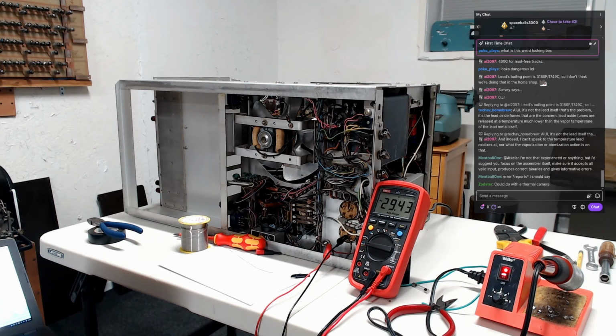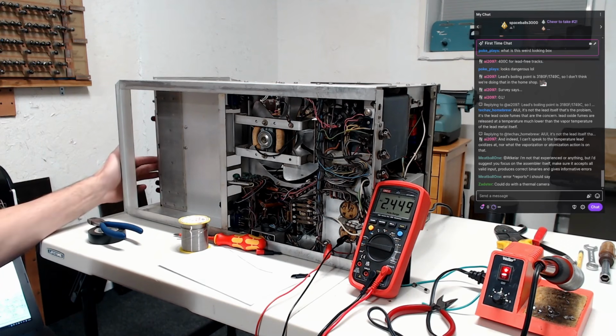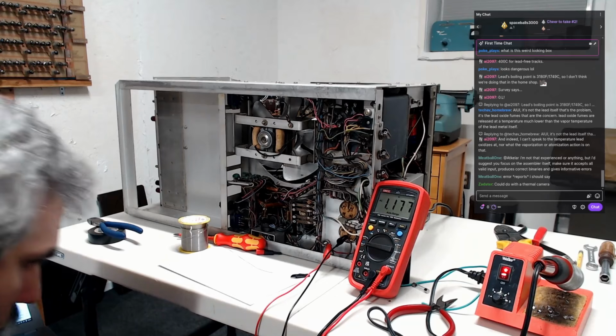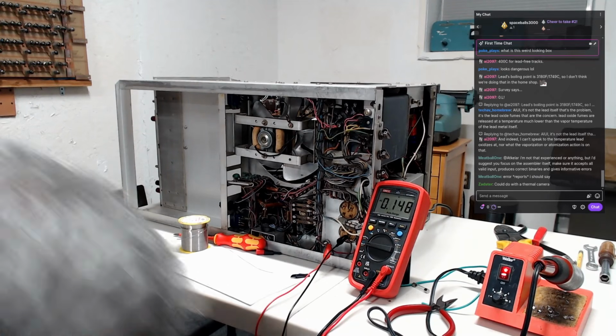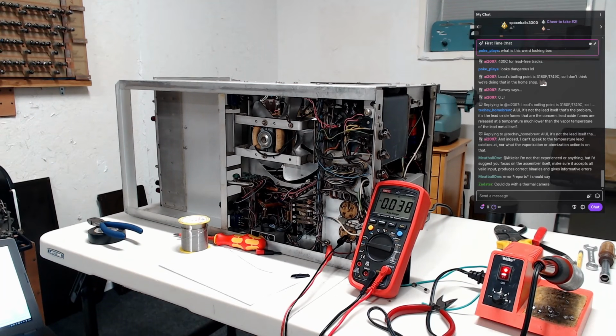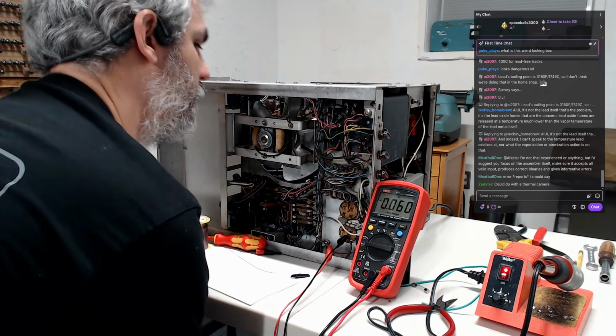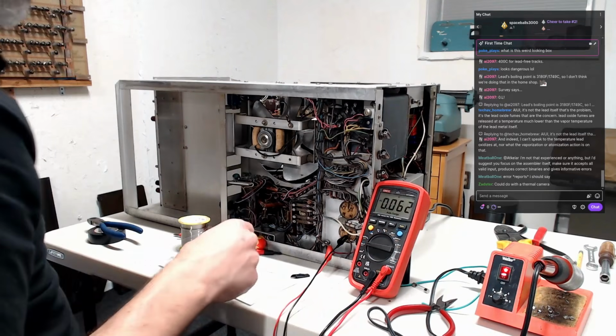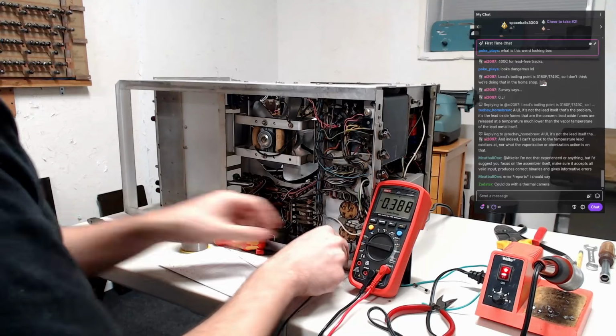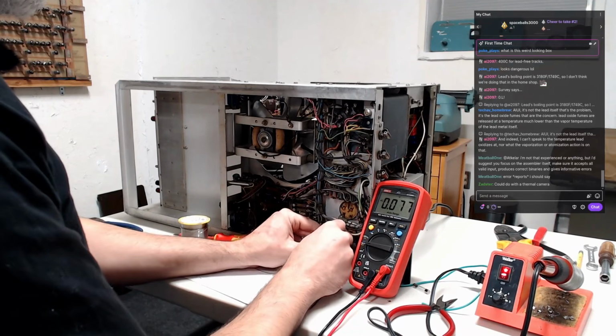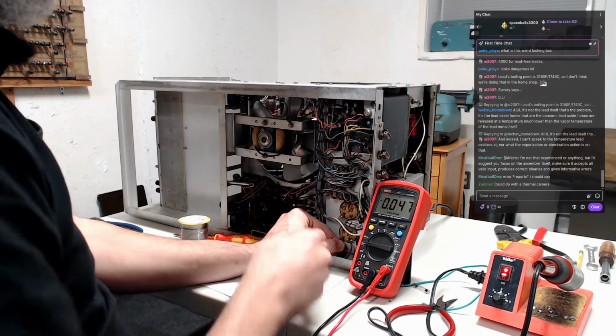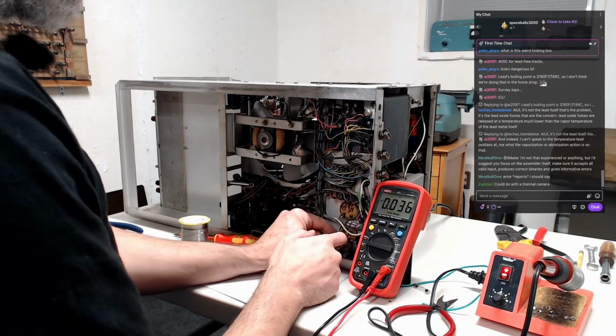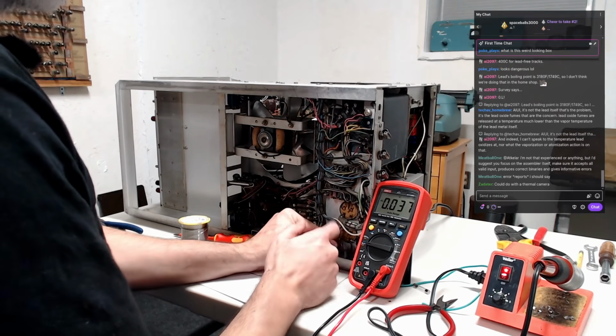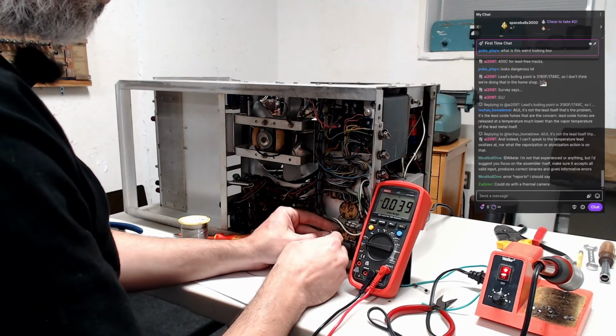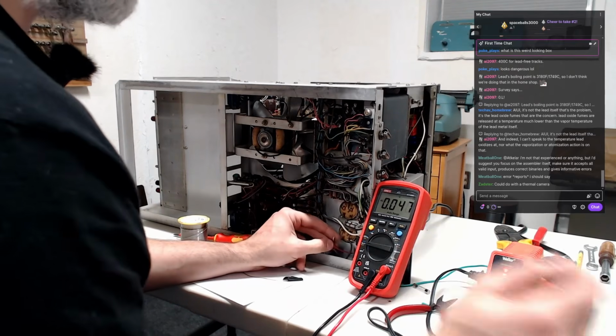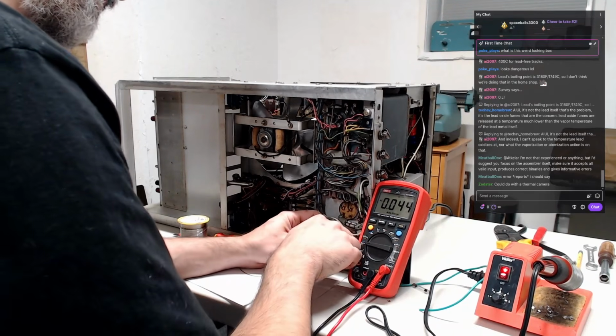So if we're stopping at 20 on the primary, that would be around 60-something volts on the secondary — pretty low. Actually we're not even getting to 20, it doesn't ever get above 12 volts on the primary. As soon as we get beyond 10, it loads up so much that even though I'm raising the variac, the voltage at the primary doesn't raise up.